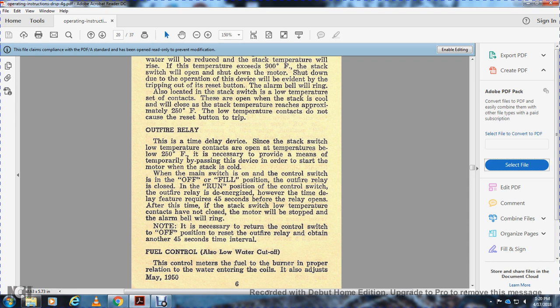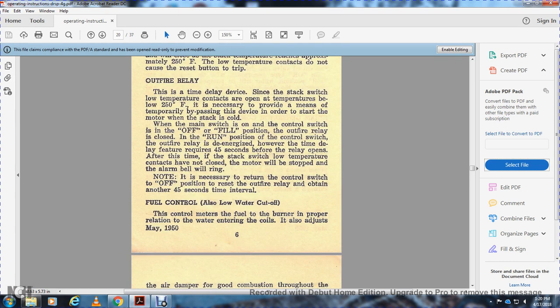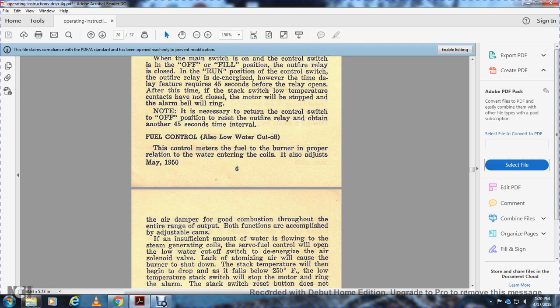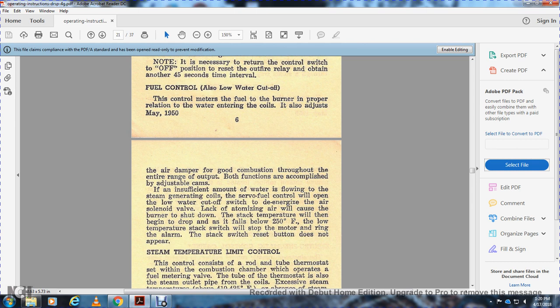Fuel control and low water cutoff. The control measures the fuel into the burner in proper relation to the water entering the coils. It adjusts the damper for good combustion throughout the entire range of output, and these functions are accomplished by the adjustable cam. If an insufficient amount of water is flowing through the steam generator coil, the low water cutoff switch opens and de-energizes the air solenoid valve. Lack of atomizing air will cause the burner to shut down.